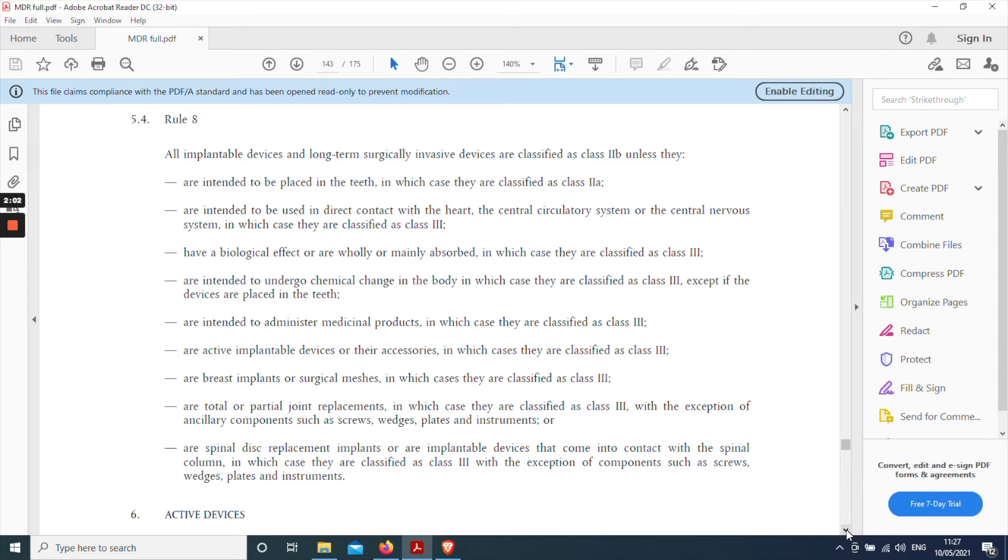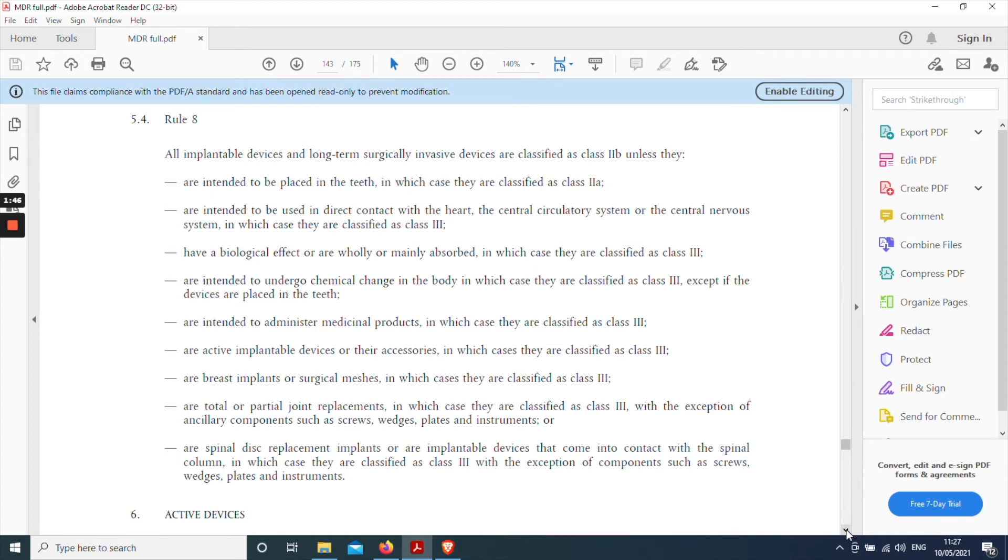So indent one unless they are intended to be placed in the teeth. Well that obviously doesn't apply to a cardiac pacemaker. Indent two unless they are intended to be used in direct contact with the heart central circulatory system or central nervous system. Now of course a cardiac pacemaker is used in direct contact with the heart and central circulatory system. So this exception does apply and on this basis a cardiac pacemaker will be classified as class 3.